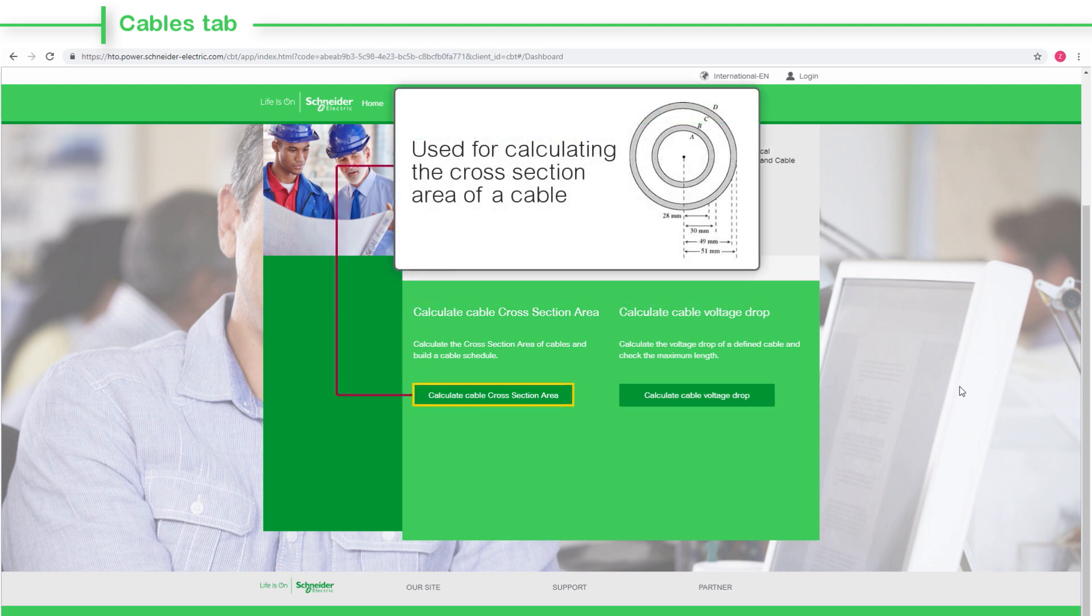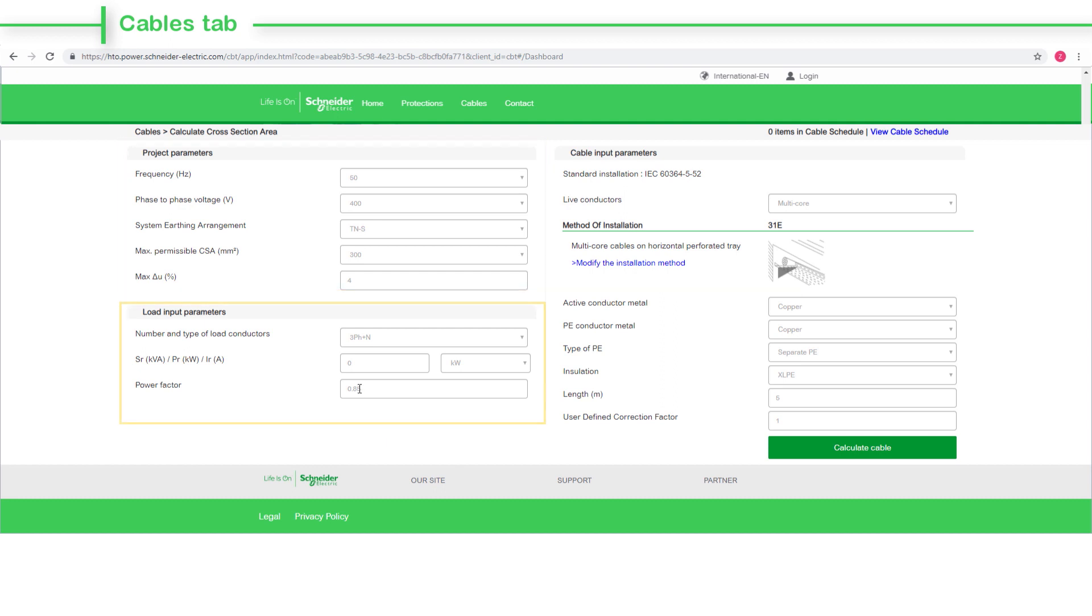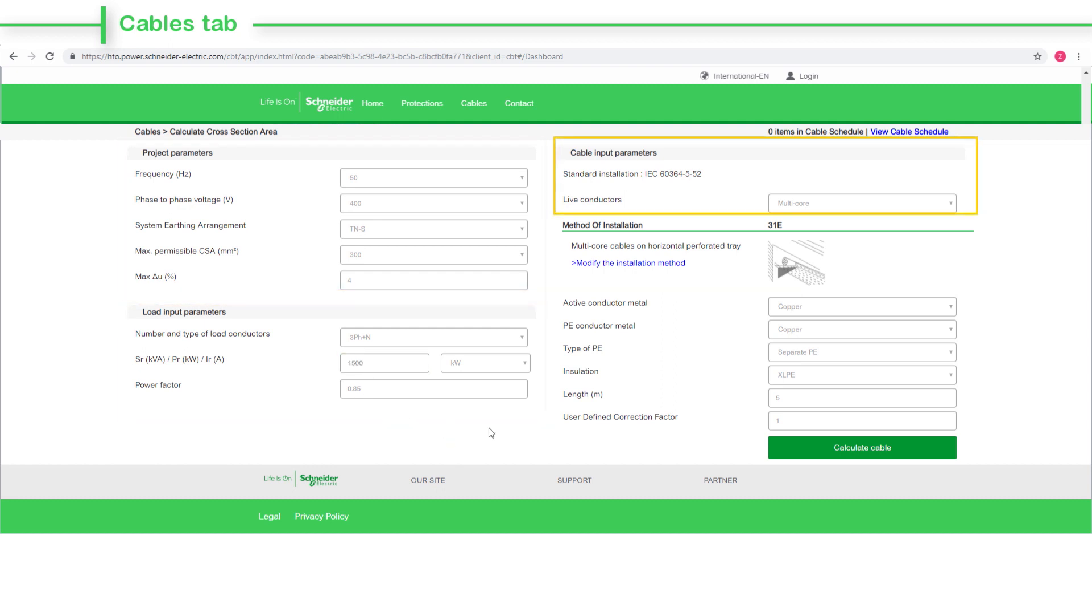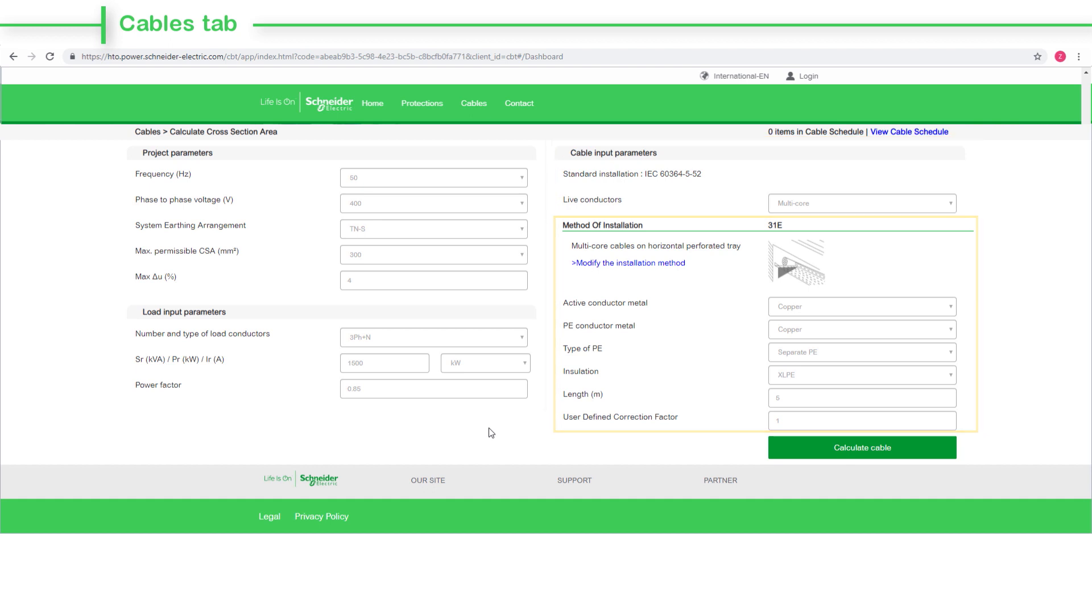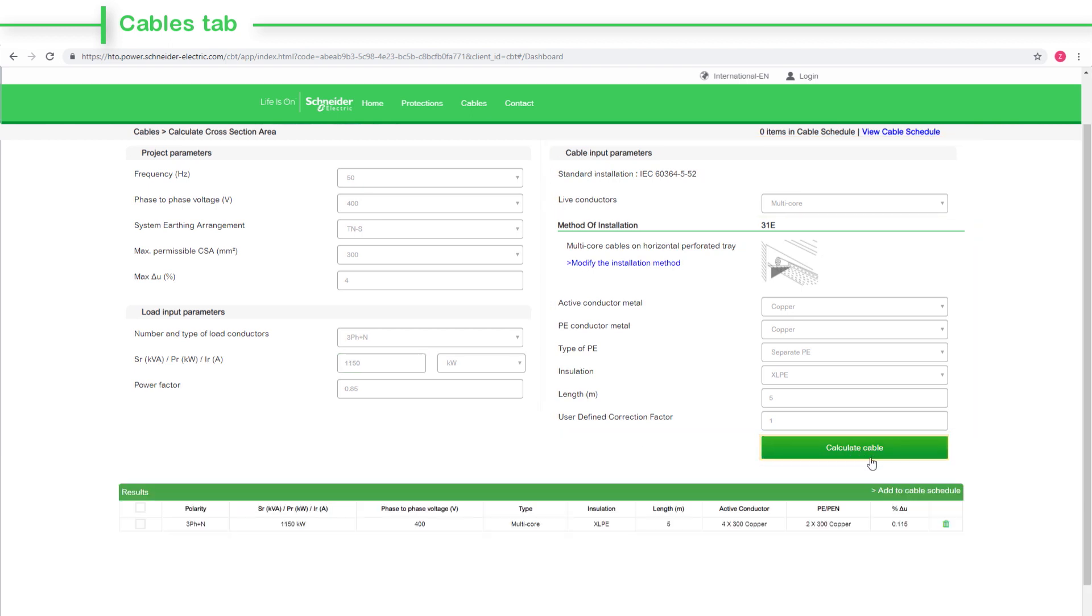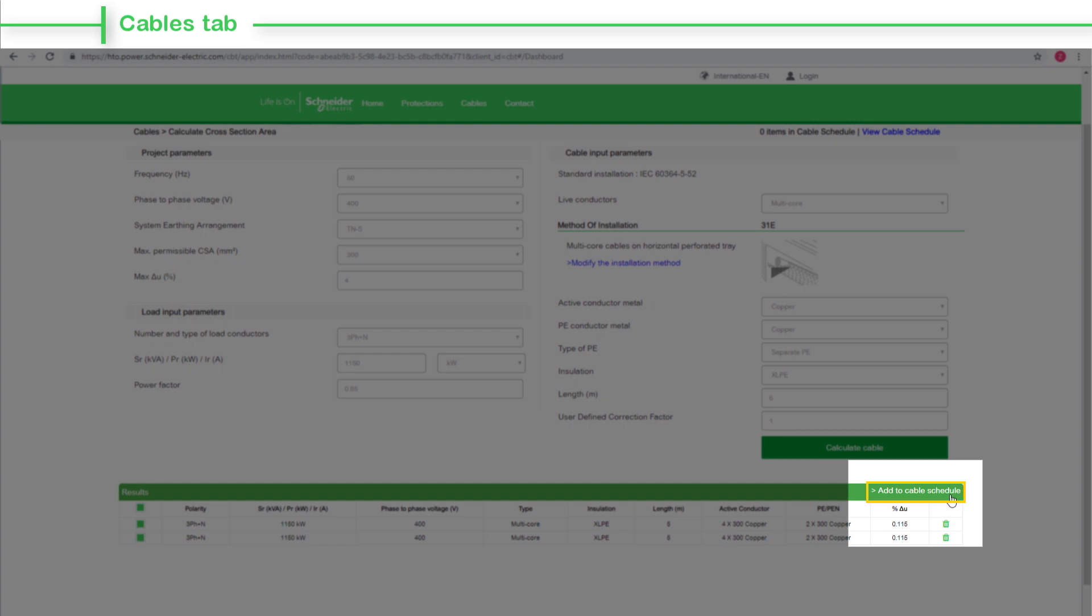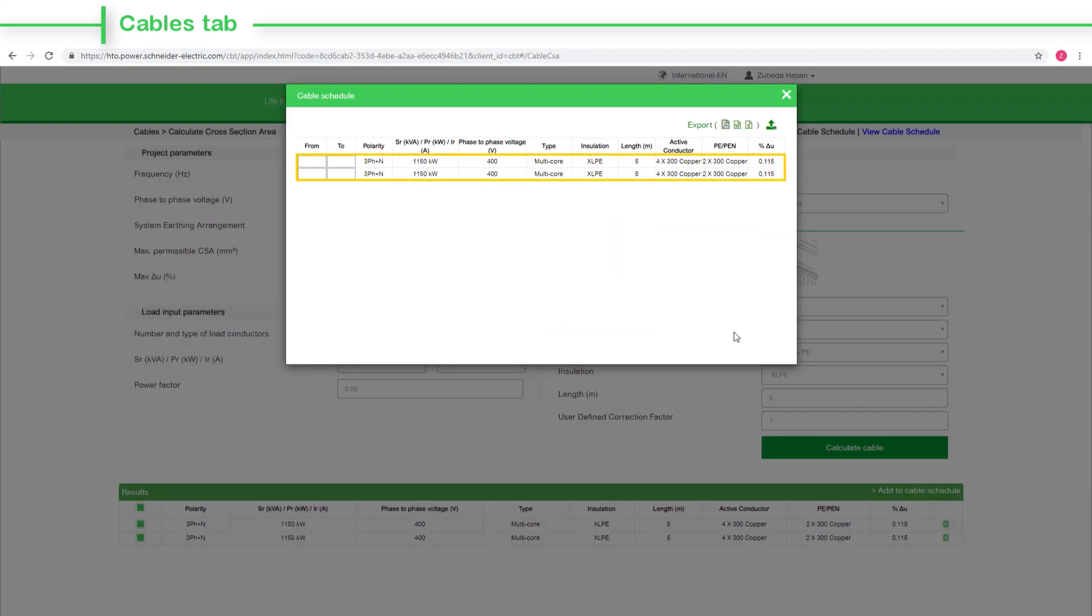Using the Calculate Cable Cross-Section Area tab, you can calculate the cross-section area of a cable. Enter all the electrical inputs under Project Parameters, Load Input Parameters, Cable Input Parameters sections. Define the method of installation, and then click the Calculate Cable button. Here are the calculation results. Once you get the results, select Add to Cable Schedule and build your cable schedule.